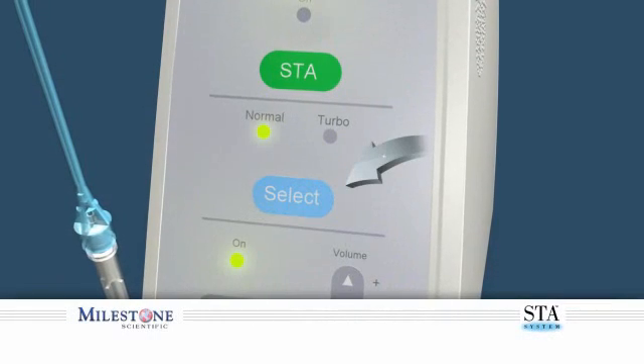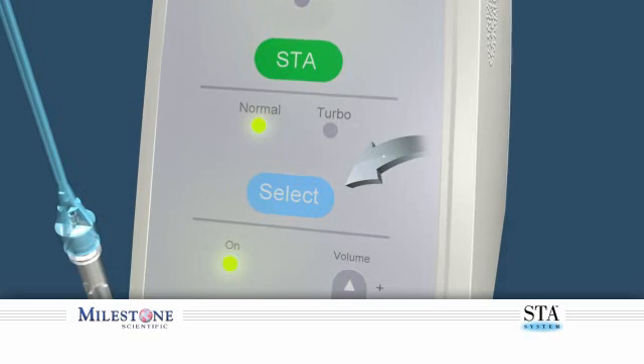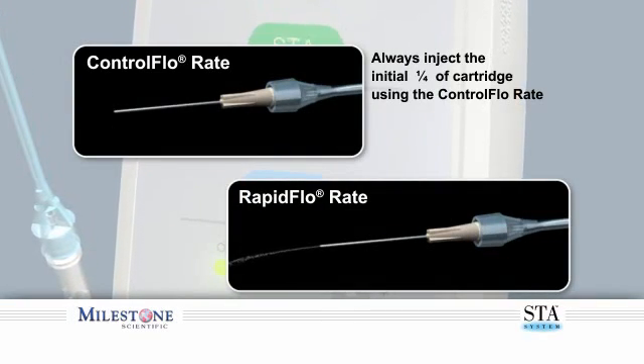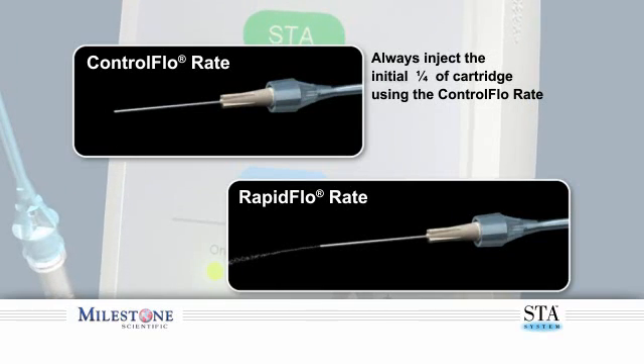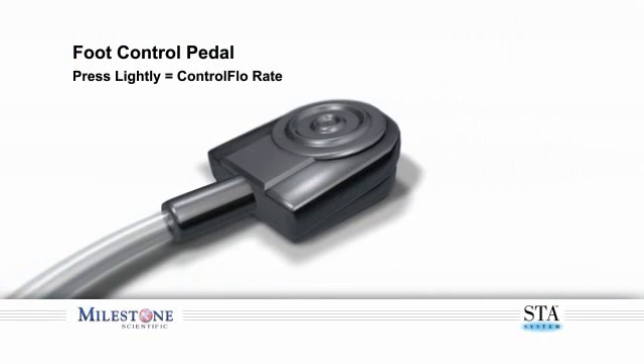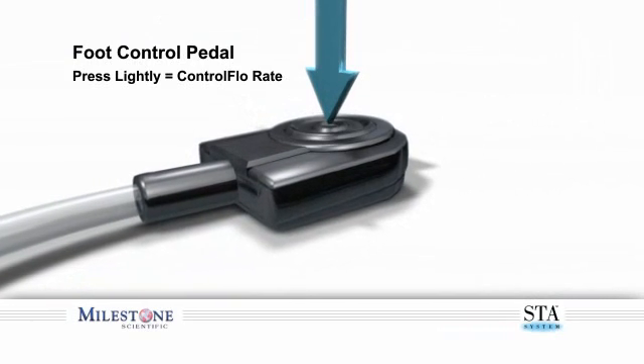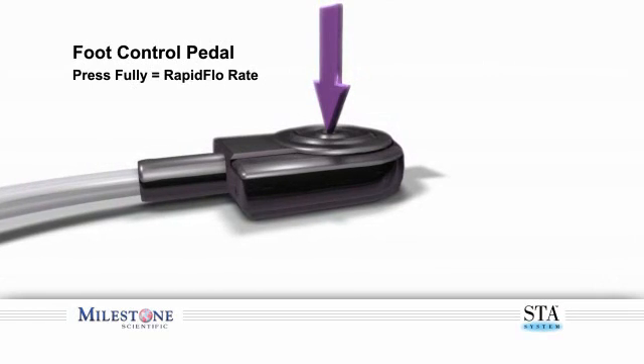Set the STA system to the normal mode, which allows the STA system to function with two distinct flow rates: the control flow and the rapid flow rate. We recommend using the ControlFlo Rate for the first quarter of the cartridge for all initial phases of infiltration and block injections. Depressing the foot control pedal lightly allows you to enter the ControlFlo Rate; fully depressing the foot control allows you to enter the RapidFlo Rate. There is a corresponding beeping tone to distinguish these two rates that you will hear.